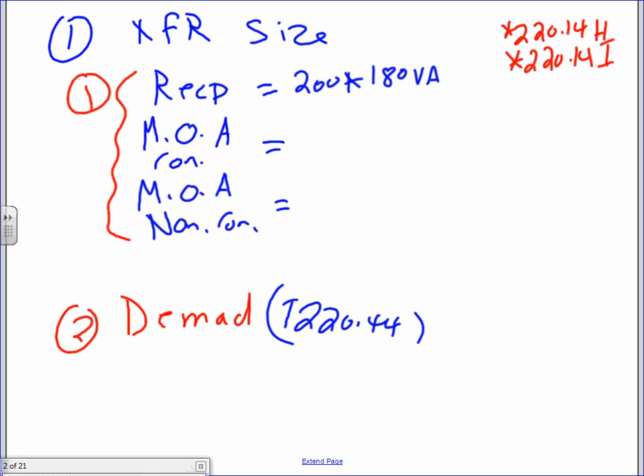Then multi-outlet assembly, simultaneously used. I have 60 feet of multi-outlet assembly. Multiply this one by the code's 180 volt-amps. 180 volt-amps, guys, they give every foot 180 volt-amps if they're simultaneously used.